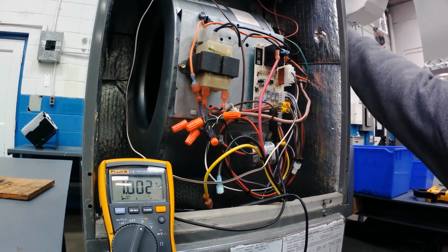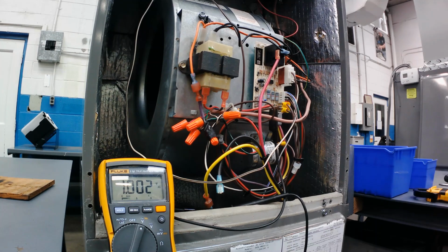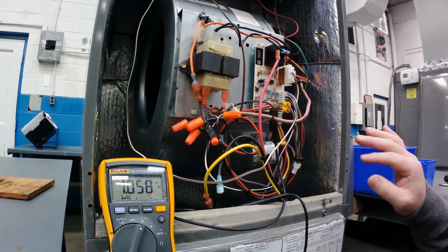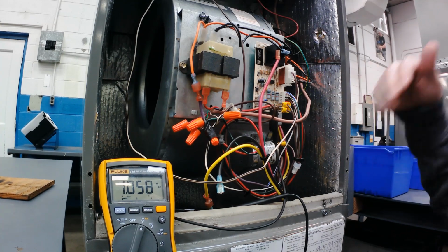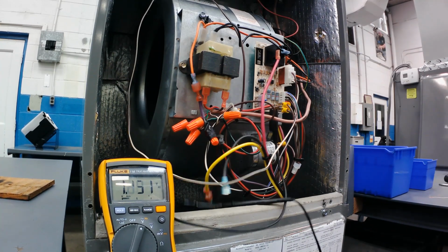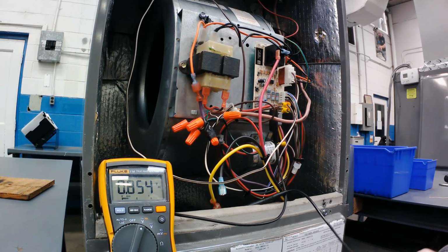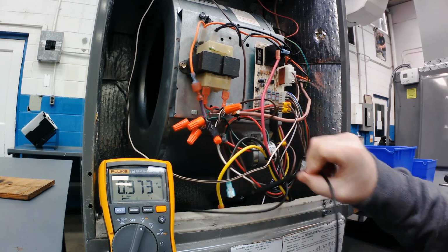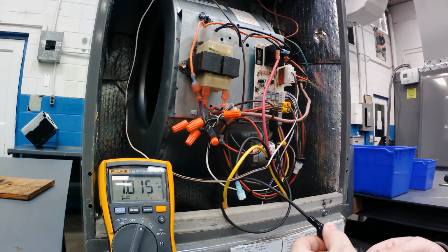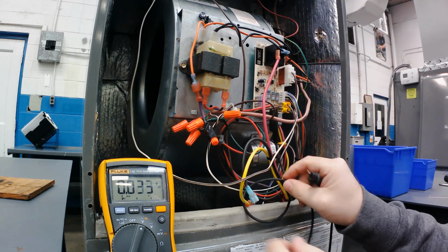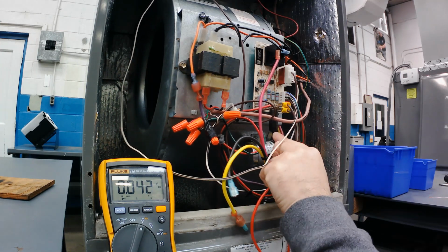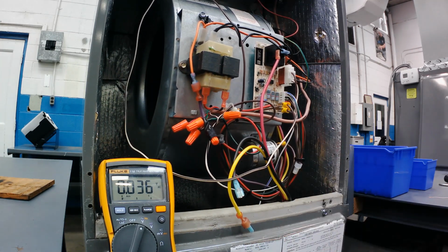While I've got it, matter of fact, let me turn the electric heat back on. All right, I'm going to do this real quick, just to show you if I wanted to check this relay in place. Now, the electric heat is on. And of course, the 24 volt signal is actually keeping that blower switch closed. But let's say that your blower wasn't actually running and you wanted to check the switch.